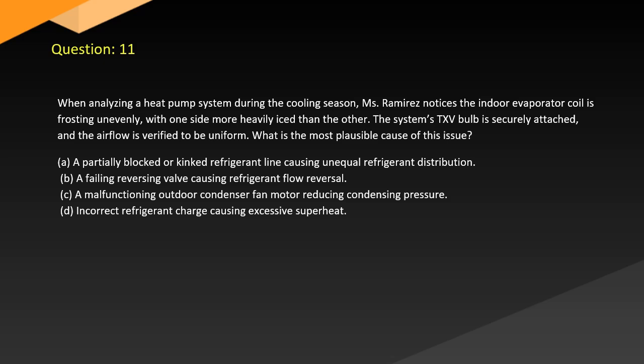Question 11. When analyzing a heat pump system during the cooling season, Ramirez notices the indoor evaporator coil is frosting unevenly, with one side more heavily iced than the other. The system's TXV bulb is securely attached and the airflow is verified to be uniform. What is the most plausible cause of this issue? A. Partially blocked or kinked refrigerant line causing unequal refrigerant distribution. B. Failing reversing valve causing refrigerant flow reversal. C. Malfunctioning outdoor condenser fan motor reducing condensing pressure. D. Incorrect refrigerant charge causing excessive superheat.